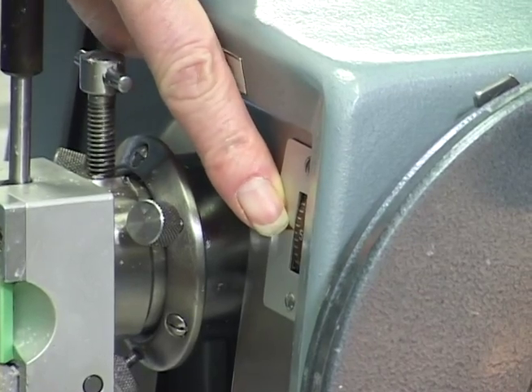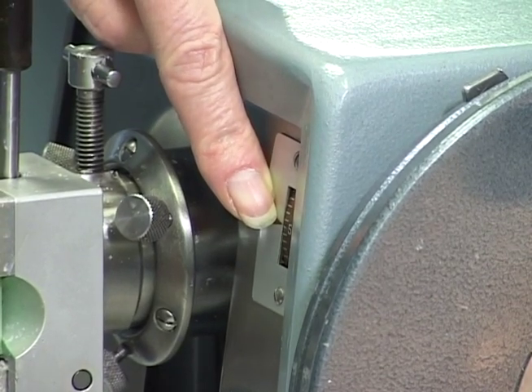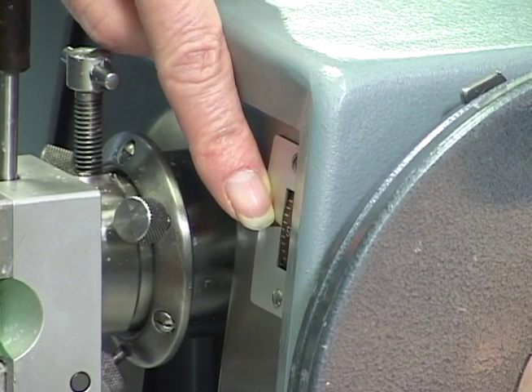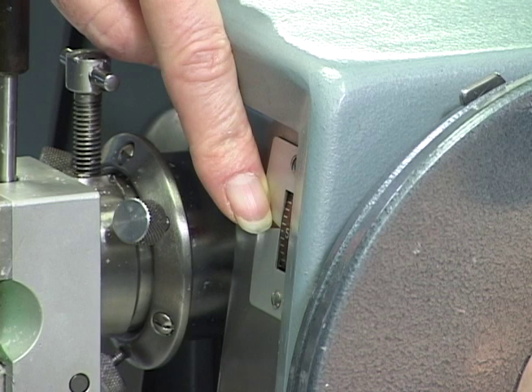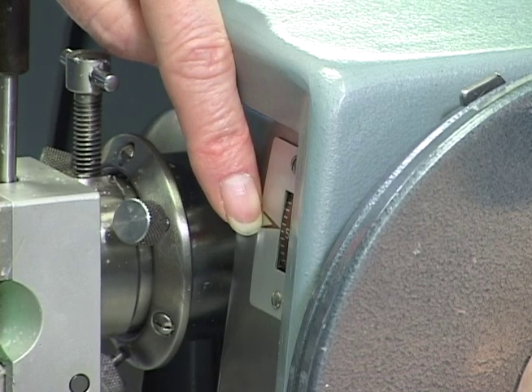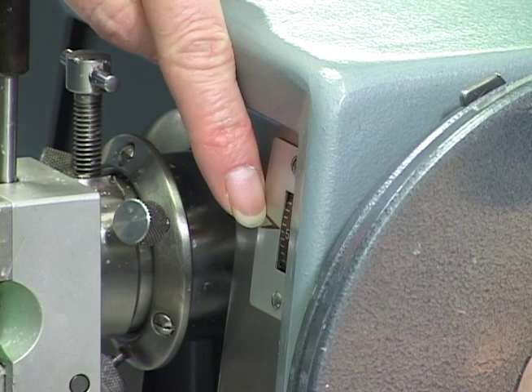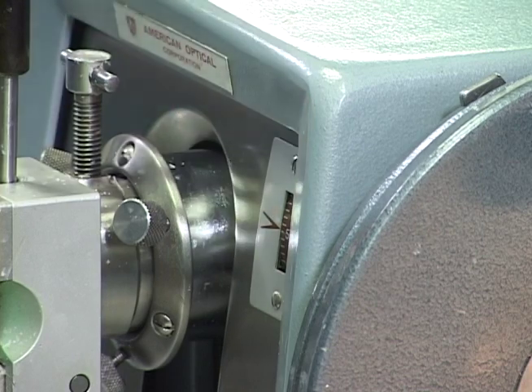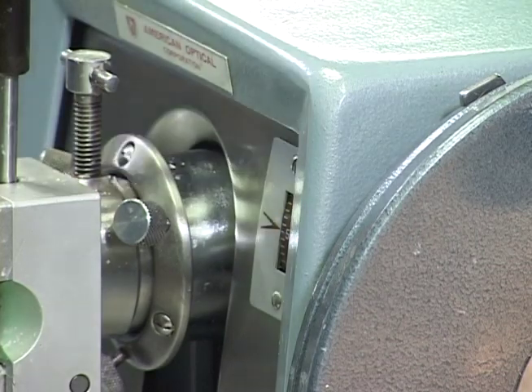Right now it's set at 5. 5 is good for things like, that's a little thick sometimes, but for our epidermal equivalents, especially some of the thinner ones, we've been doing it at 5 because they've got a plastic sheet on the bottom. For some reason they tend to be very wavy, and we haven't found a way to overcome that. For some reason, cutting them at 5 rather than 4 or 3 like I would like to do has helped them flatten and overcome that. I can't explain fully why, but that's been working and everybody's had much better results since I've done that. So even though my ribbon looks smooth, the tissue itself hasn't been reacting nicely.